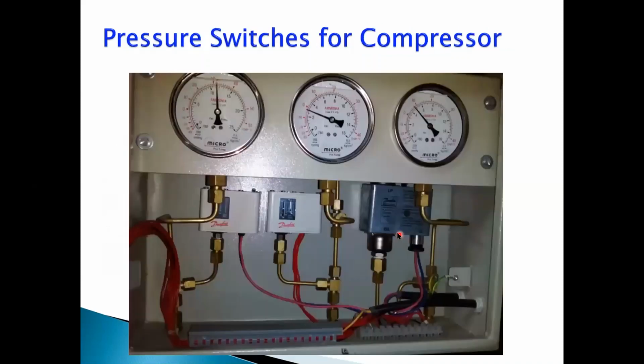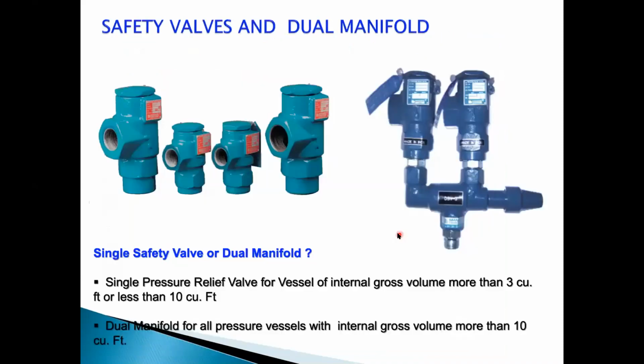Then we'll talk something about safety parts, like we have safety switches in the compressor to protect the compressor from low suction pressure, high discharge pressure, or oil differential pressure. Safety valves are the most important thing: your plant has to be protected, and the pressure vessels have to be protected with a dual manifold and safety valve. The function of the dual manifold is that one valve is connected and one valve is bypassed. So when one valve pops up, we can operate the spindle and take the valve out for servicing or replacement.